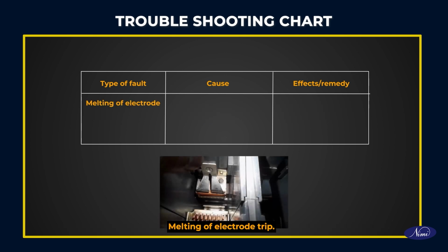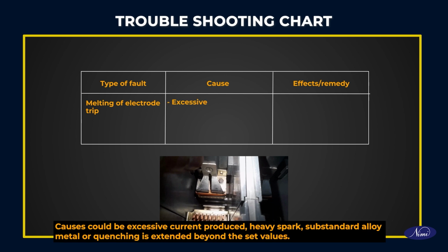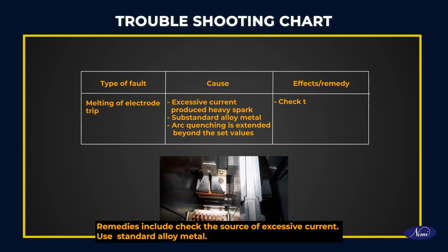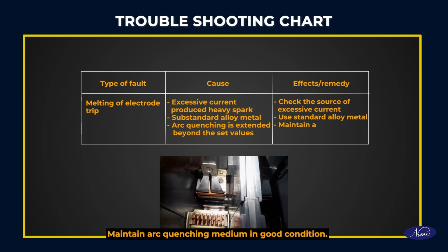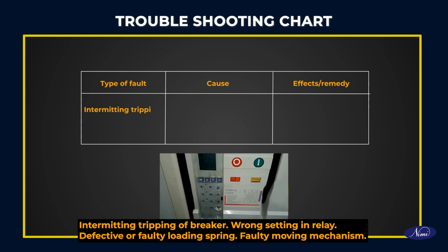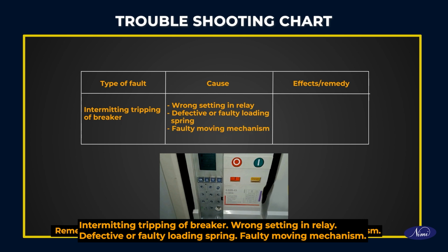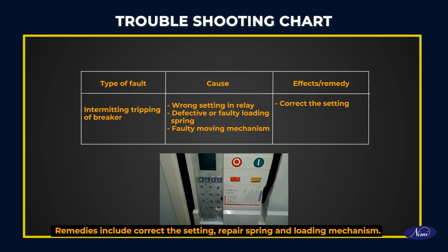Melting of electrode tip. Causes could be excessive current produced, heavy spark, substandard alloy metal. Arc quenching is extended beyond the set values. Remedies include check the source of excessive current, use standard alloy metal, maintain arc quenching medium in good condition. Intermittent tripping of breaker. Causes: wrong setting in relay, defective or faulty loading spring, faulty moving mechanism. Remedies include correct the setting, repair spring and loading mechanism.